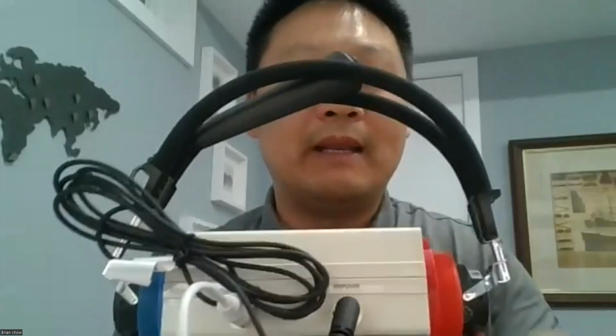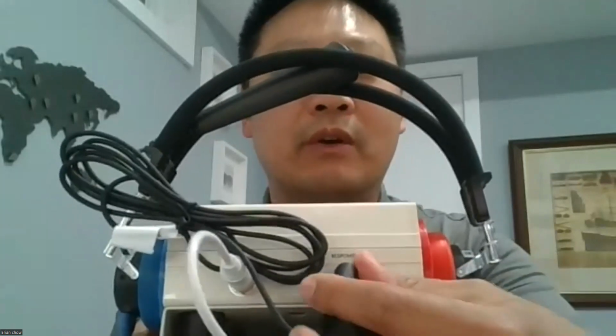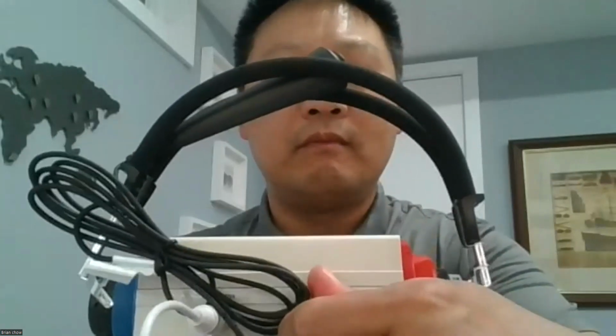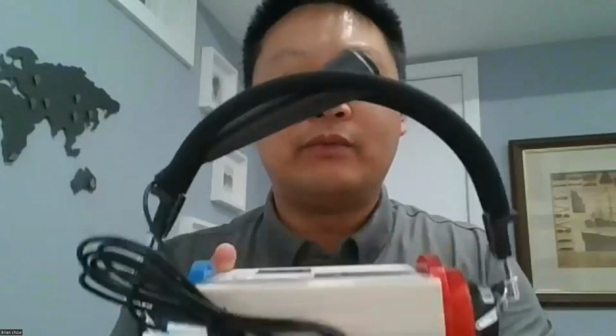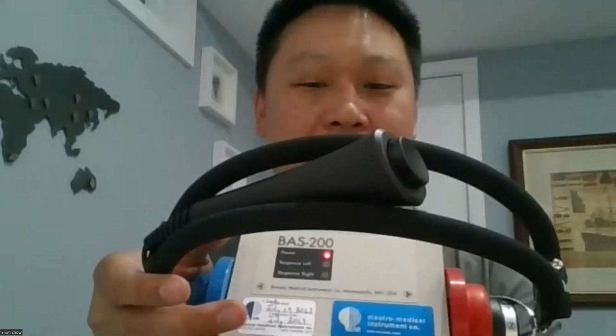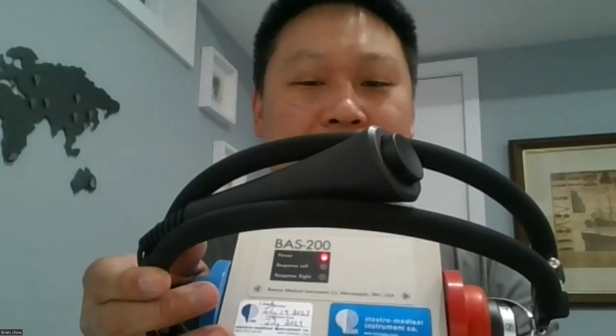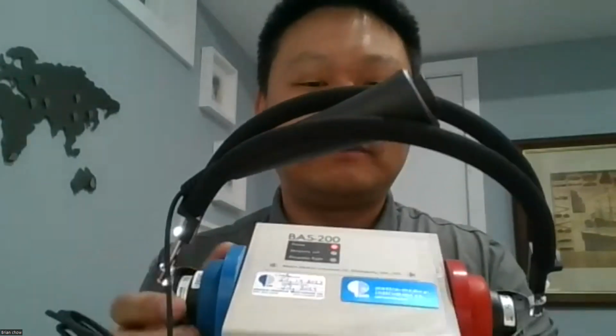Secondly, we need to make sure that the patient response button here is also removed. And when it's removed, we will see that the BAS 200 light is activated. Lastly, because we're using a sound booth, we need to make sure that the sound booth door is closed. Now we'll get into the software.